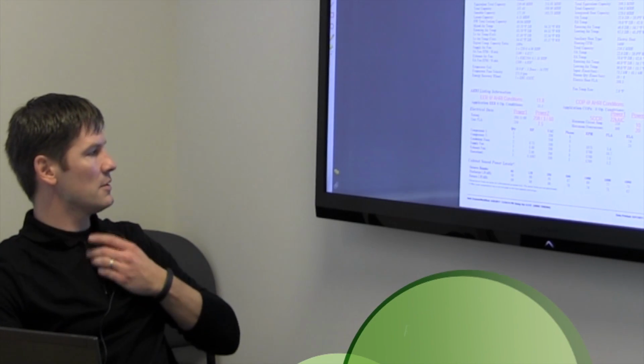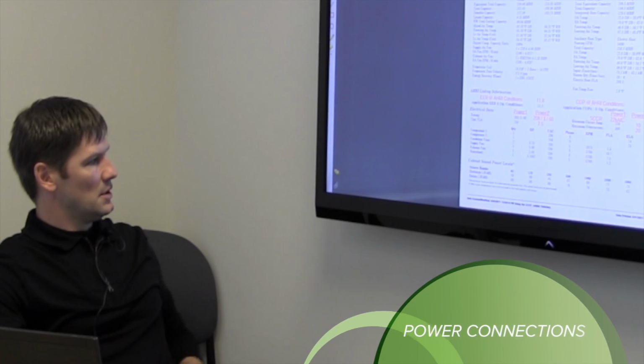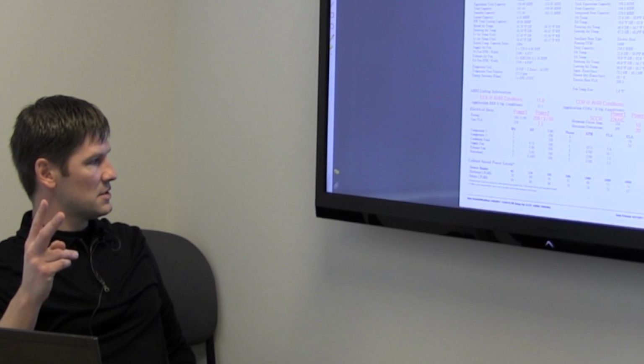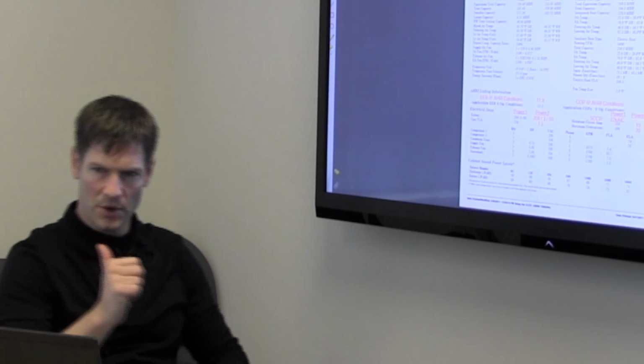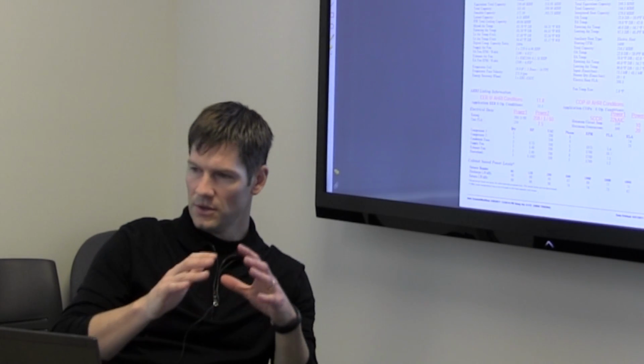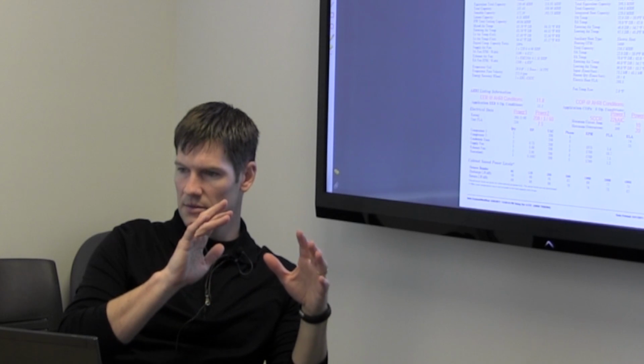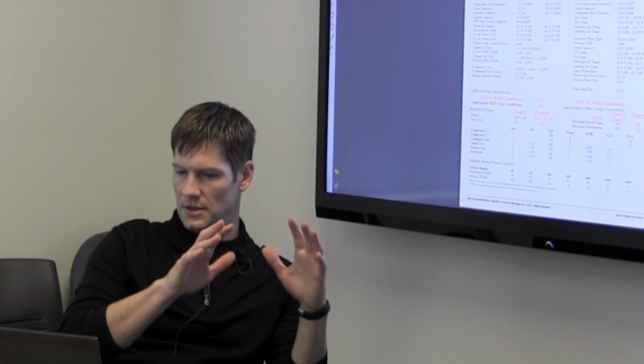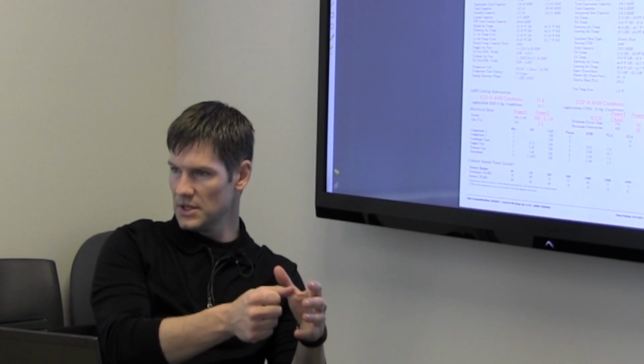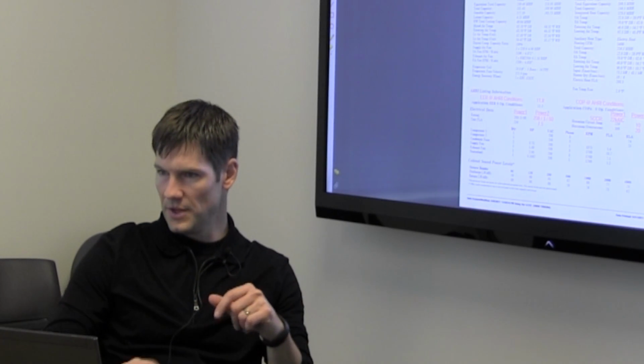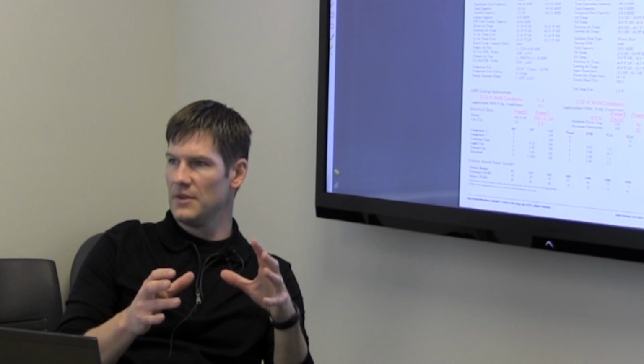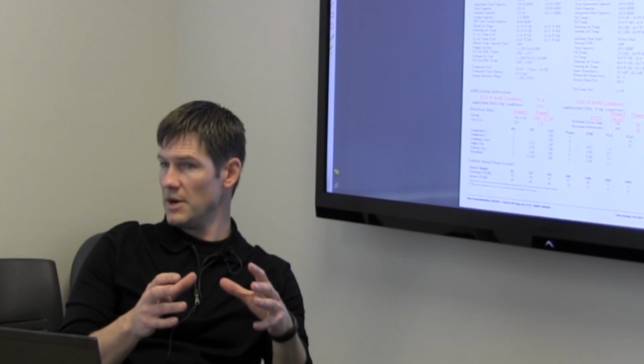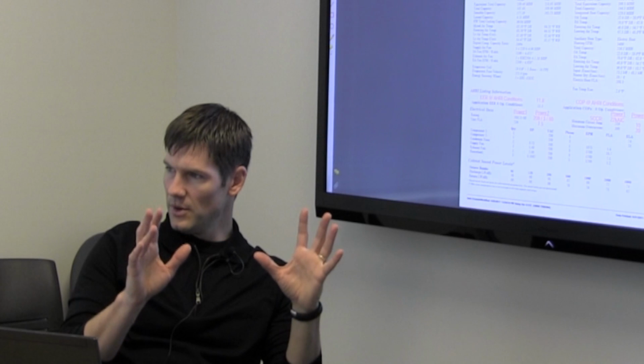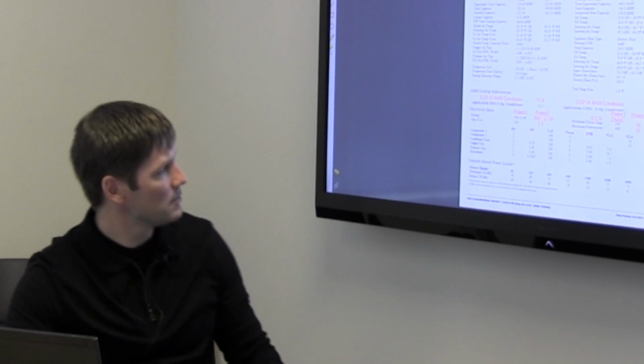These have 2 power connections. So they have 2 disconnects, and that's for smoke evacuation, I believe. So the controls, supply fan, and heat pump are all on one disconnect. The exhaust fan is on a different disconnect. So that way, I think they might have the exhaust fans powered off emergency power or something, so that if the power were to go out in the building, they could still evacuate smoke.